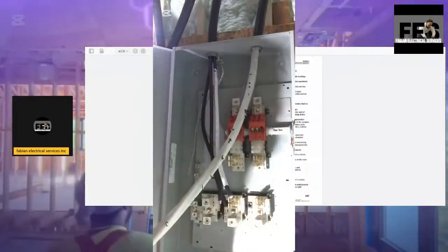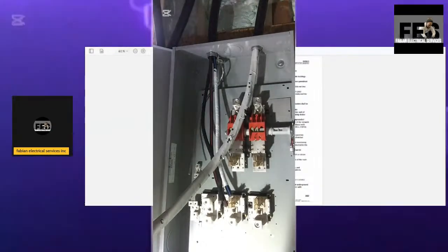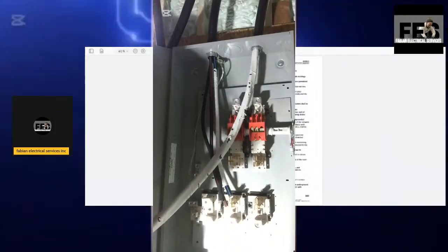We call it Teck cable, and there are parallel runs being run from the outdoor meter base. Again, what I like to do with an installation like this is keep that white sheeting on until I land my conductors inside of the panel. Then I'm going to remove that white sheeting. I also make sure to put my ground bushing on first.